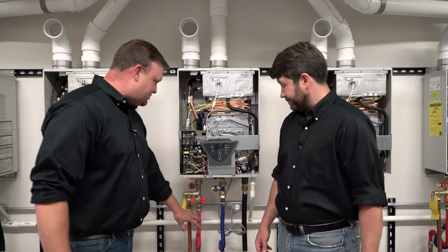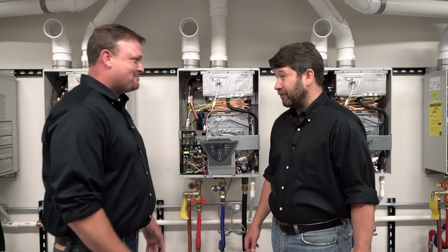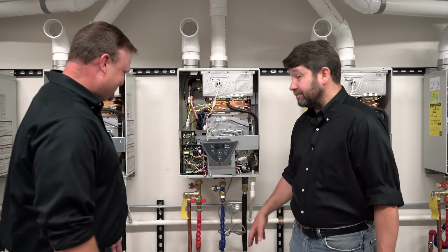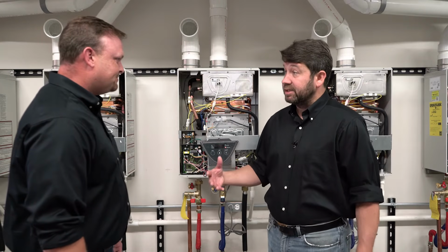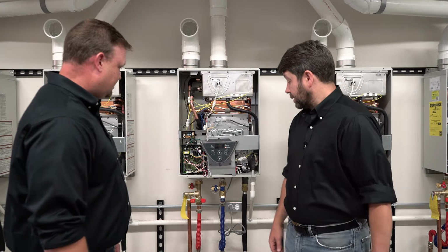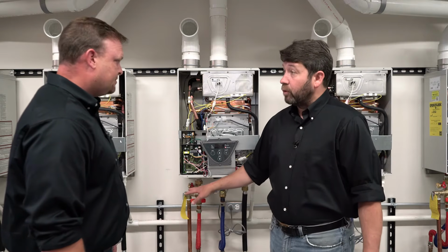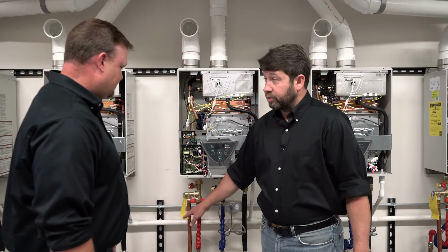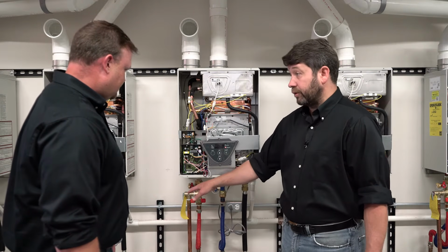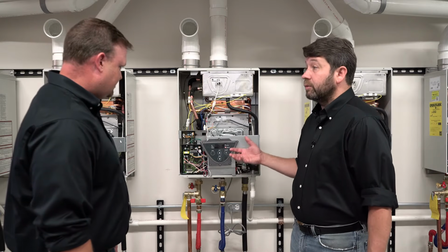It's easy for us because we've got red and blue here. Yeah, we've color-coded these to make it easy, but that goes to say exactly how easy it is to accidentally get these reversed. Okay. So once we do that and we can get flow going through the water heater, and flow is either coming out of our pressure relief valve or out of our service port through our hose, the water heater should come on and operate.